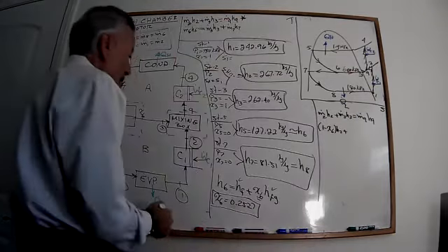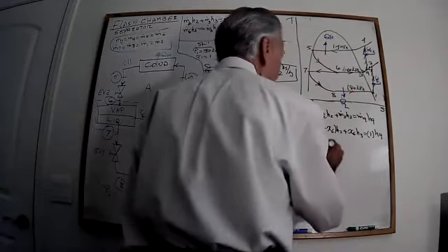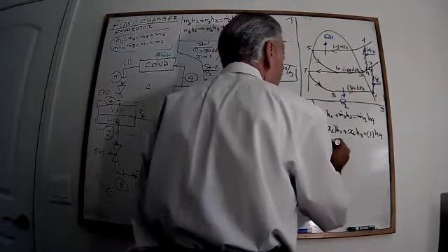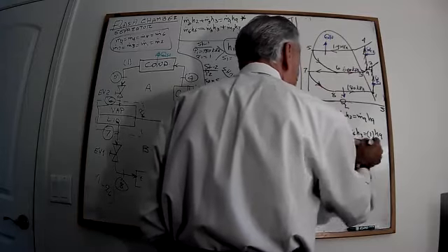Now I'm looking at that. I have H2 and H3. I just calculated the value of X6. What's unknown here? H9, that's only 1. So from there, I can find the value of H9 to be 266.38 kilojoule per kilogram.